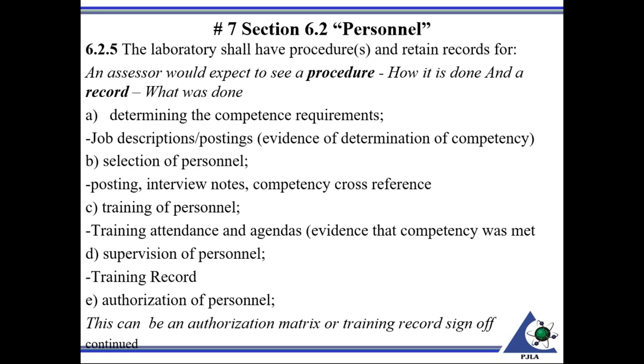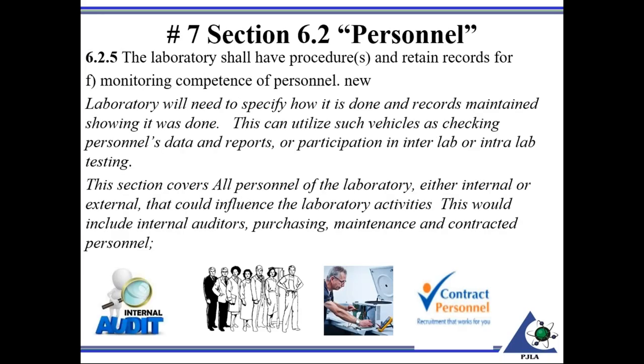Authorization of personnel. When someone is fully trained, and you want to authorize them to perform a specific test or calibration, that's a record that needs to be captured. This could be a simple authorization matrix, or just a training record sign-off that authorizes an individual to perform a test or calibration on behalf of your organization.